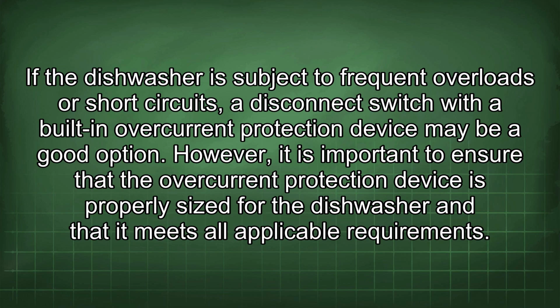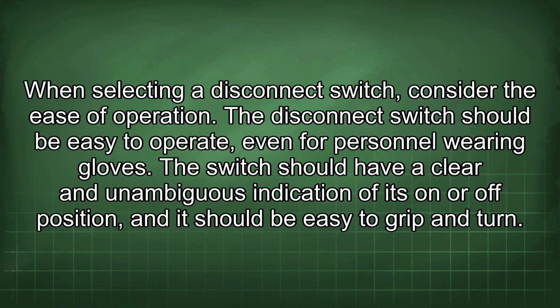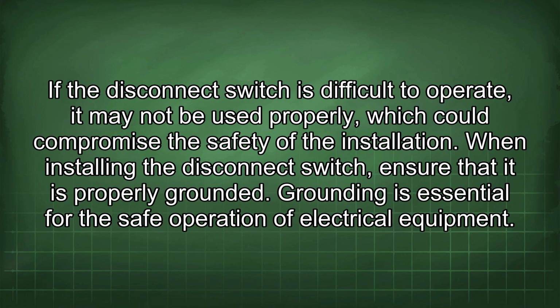When selecting a disconnect switch, consider the ease of operation. The disconnect switch should be easy to operate, even for personnel wearing gloves. The switch should have a clear and unambiguous indication of its on or off position, and it should be easy to grip and turn. If the disconnect switch is difficult to operate, it may not be used properly, which could compromise the safety of the installation.